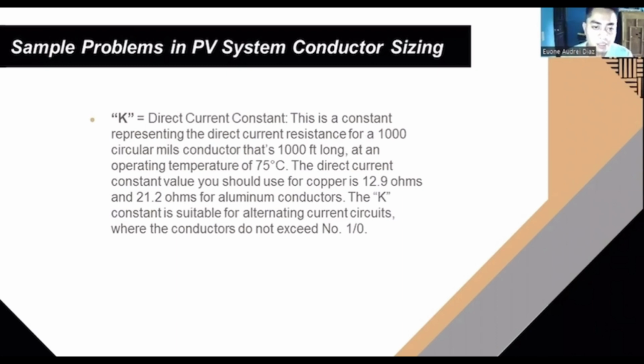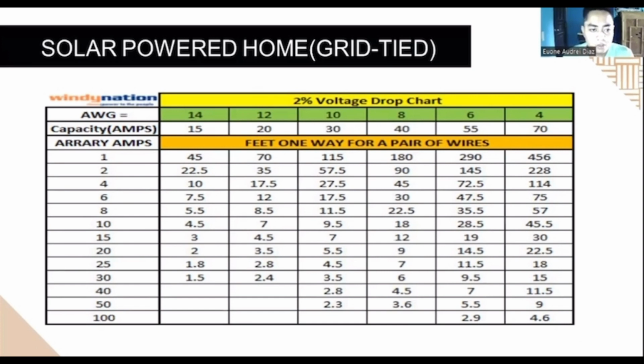K is the direct current constant. This is the constant representing the direct current resistance for 1,000 circular mils conductors that are 1,000 feet long at an operating temperature of 75 degrees Celsius. The direct current constant value usually used is 12.9 ohms for copper and 21.2 ohms for aluminum conductors. The K constant is suitable for alternating current circuits where the conductors do not exceed number 1/0. This is the table of wire sizing for the example, with 2% voltage drop and the one-way length of wires, with the AWG and the ampacity in amps.